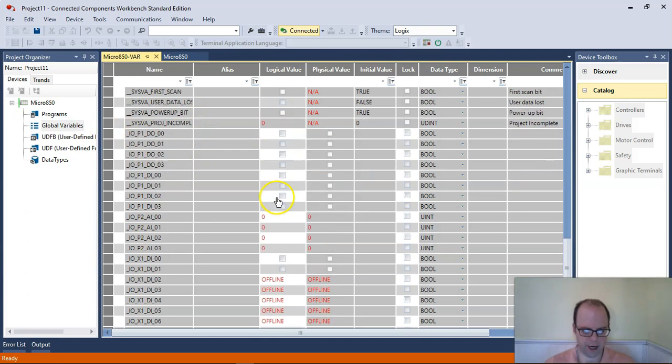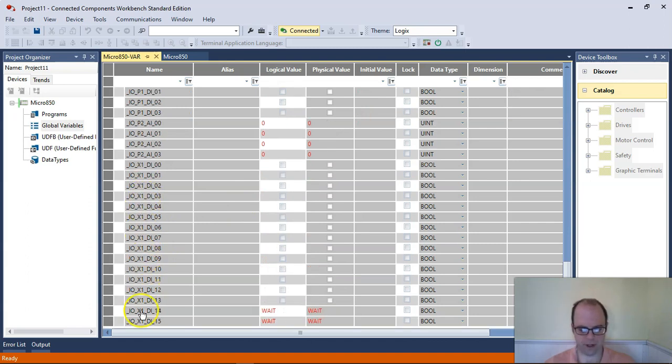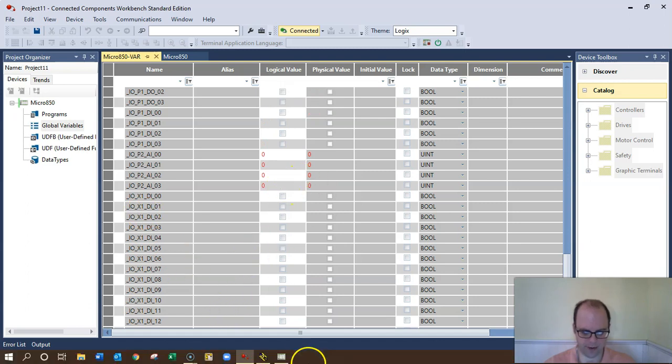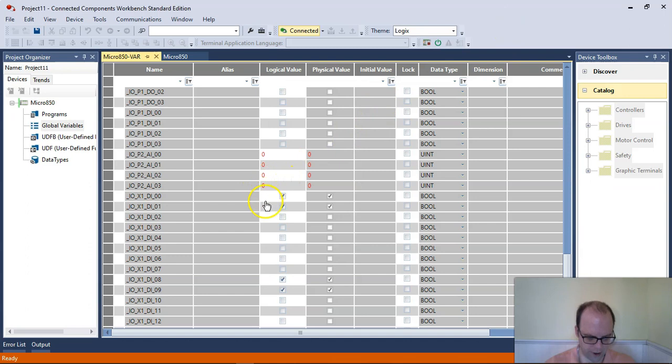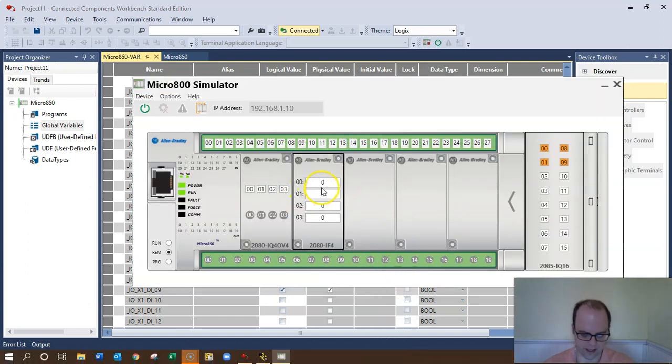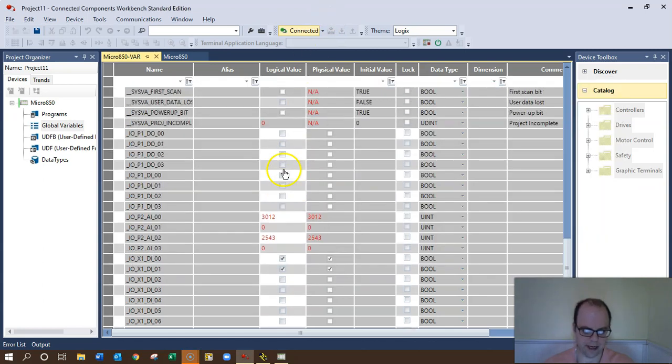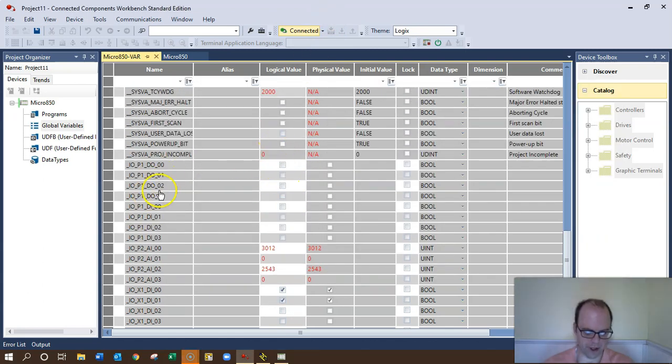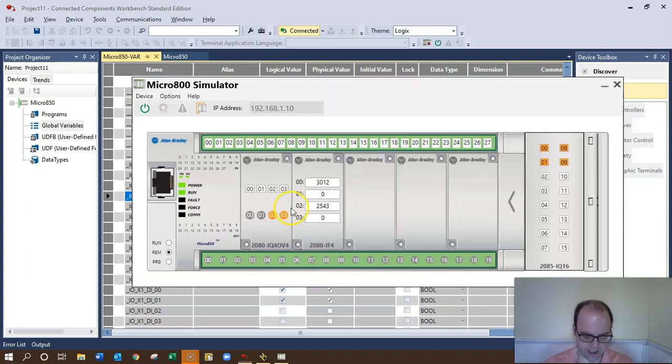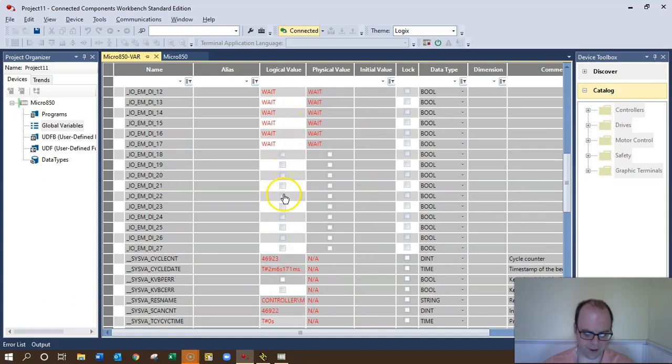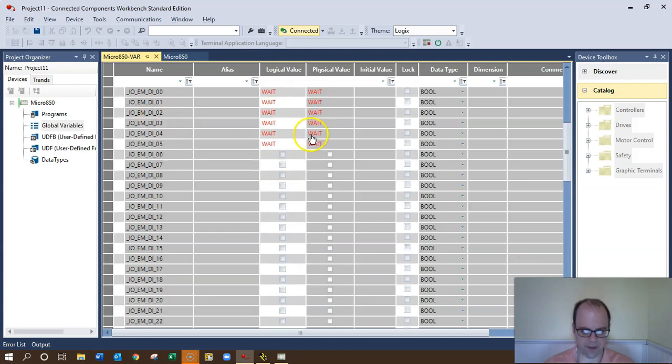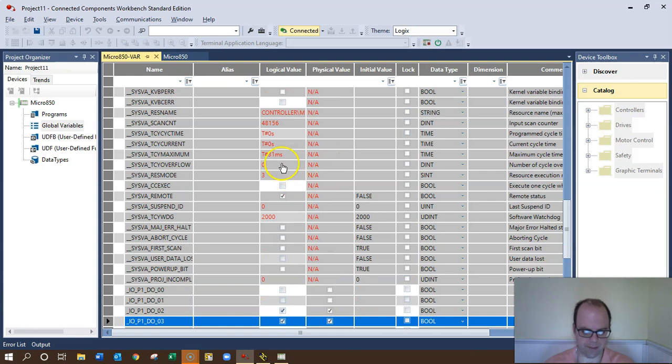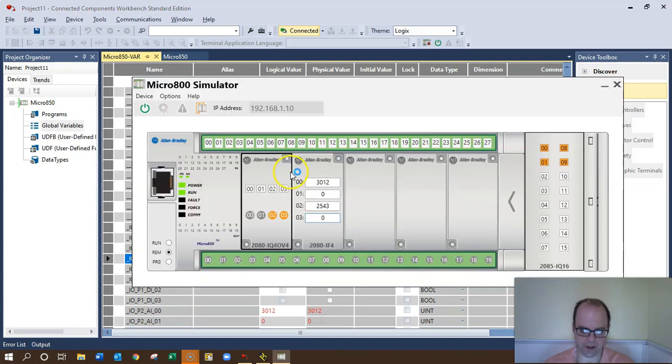And now everything's hunky dory. If I wanted to turn these on, I can. Let me go to my global variables. And you can see it's being read right now. It's X1. So it's slot one would be X1. So you can see that's where everything is. If I go into here and start clicking these on, you can see that the value is now on. Those physical values. If I go back to my processor, I could put in some random numbers here that would simulate the analog input. And you can see that connects right here. If I want to turn on an output, I could literally just click these outputs on. And look, these outputs turn on.